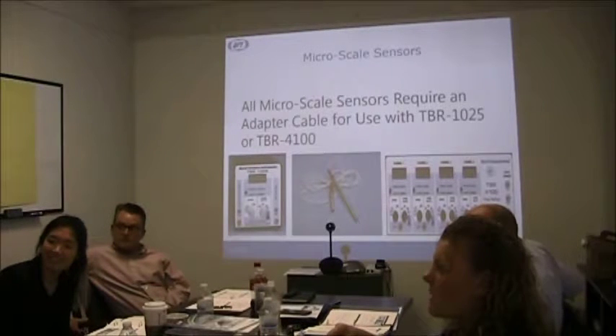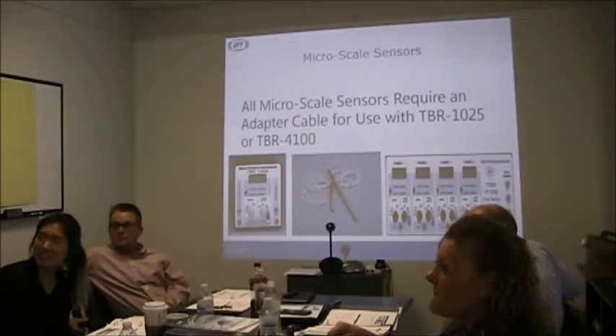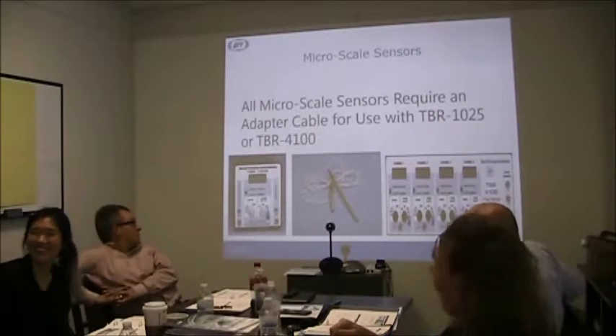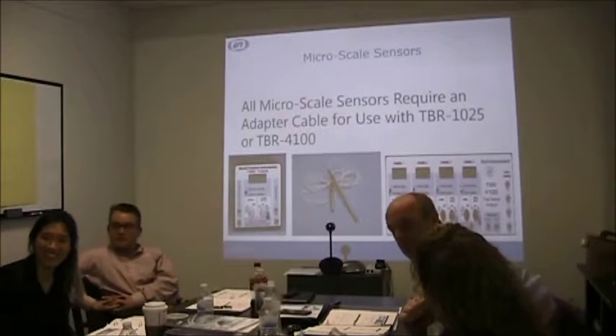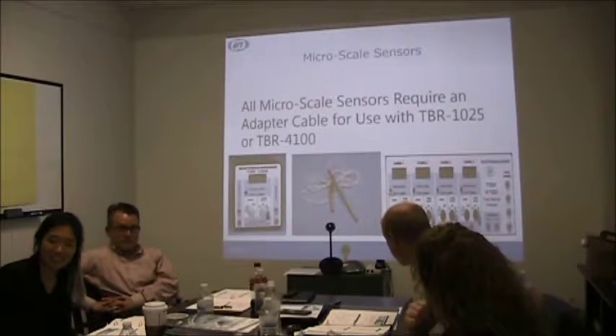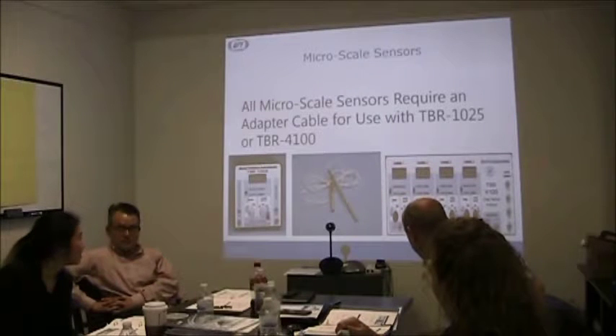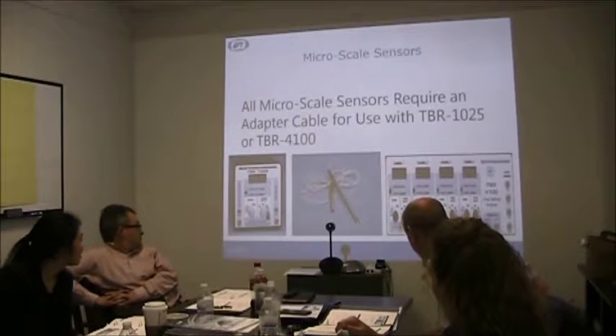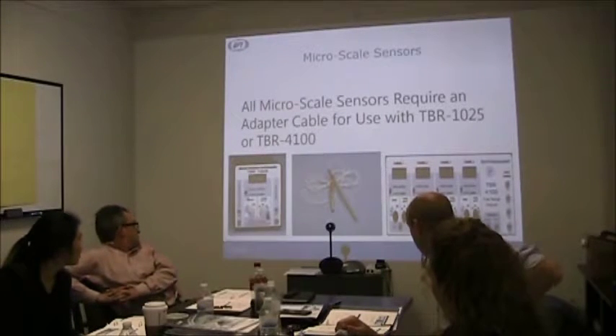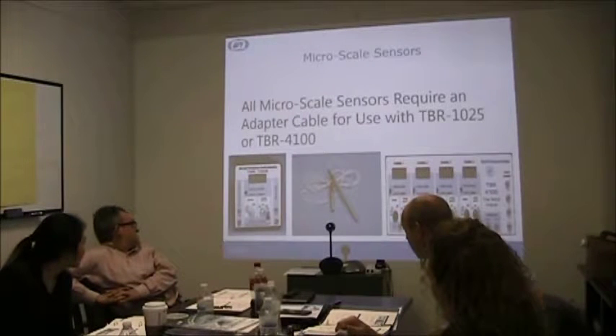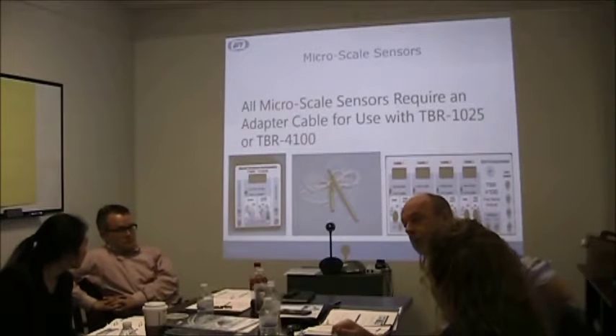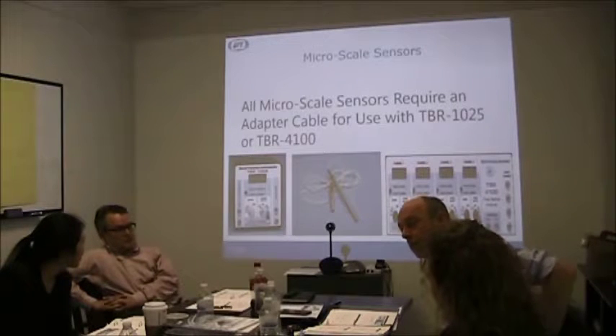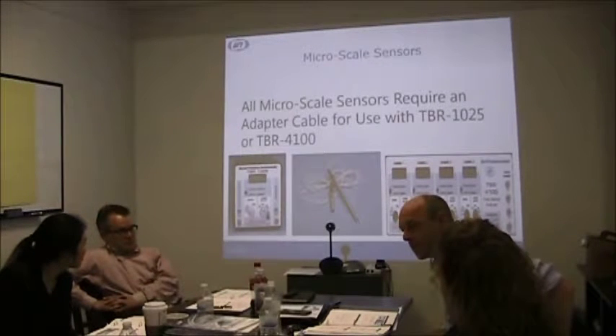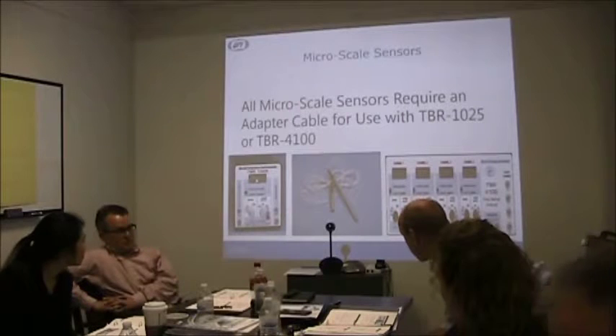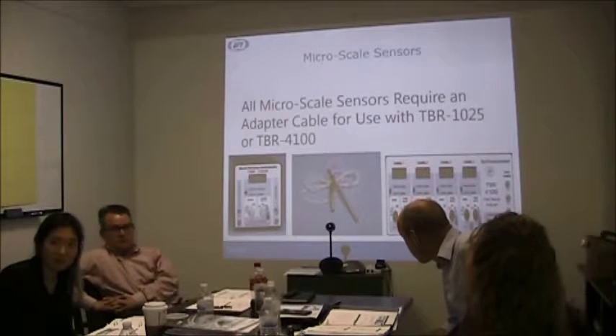This is just selecting, I thought it was poise select, sorry. No, it was probe select, I got it. But one good thing that I haven't mentioned yet on here: the switch is nominally in the down position for output current, but when you flip this up to applied voltage, you can verify, as the instrument is supposed to be, that nitric oxide is supposed to be 860 on this display, hydrogen sulfide is supposed to be 150 on this display, just like it is in the manual.